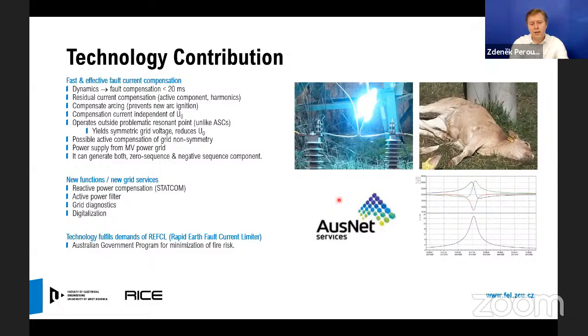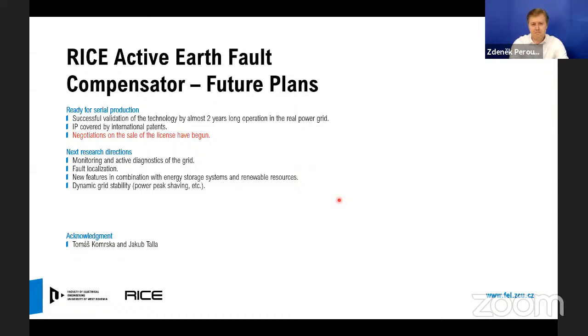What is an important result? Our device fully complies with the very strict demands of the Australian Rapid Earth Fault Current Limiter for minimization of the risk of fire. So we are able to comply with these strict requirements. What are the future plans? We are at the moment ready for serial production. We successfully passed the validation of the technology by almost 2 years of operation in the real power grid. The technology is covered by international patents, and we already started a negotiation on the sale of the license. So I hope that we will be on the market very soon.